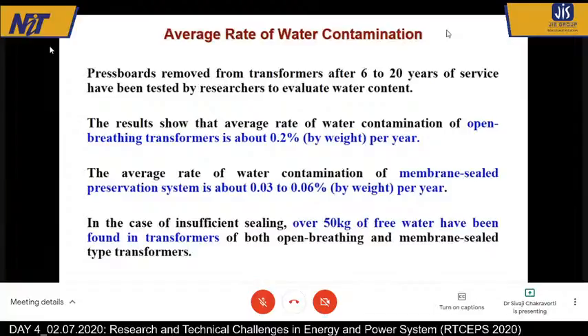An open breathing system, again, for my participants, I want to say that the transformer has a breathing system. We have the conservators and breathers. Open breathing means that the oil in the conservator tank at the top is in touch with the air through the breather, of course. In an open breathing system, it has been found that moisture can come in in spite of you giving silica gel and everything, whatever you have learned in your life. It will be around 0.2% by weight per year. So that means in 5 years, 1% by weight of moisture can come in. But that is when people have taken good care.